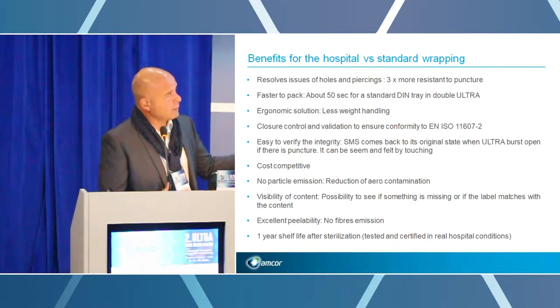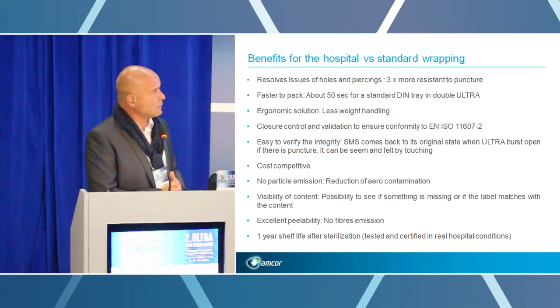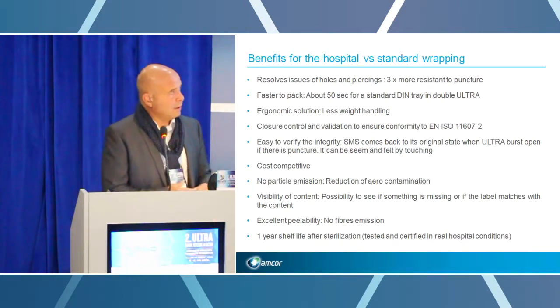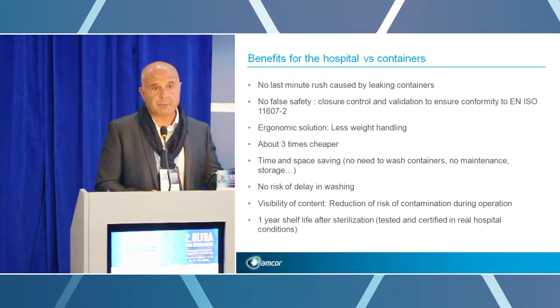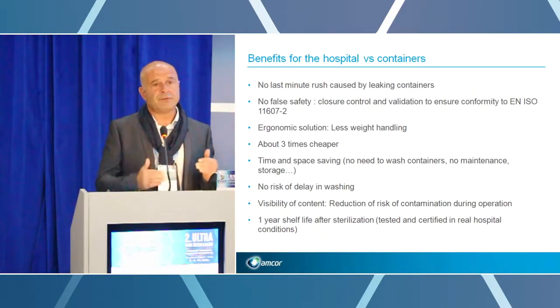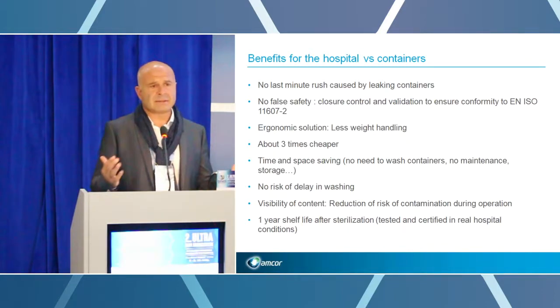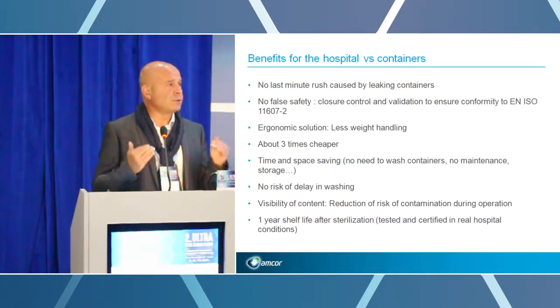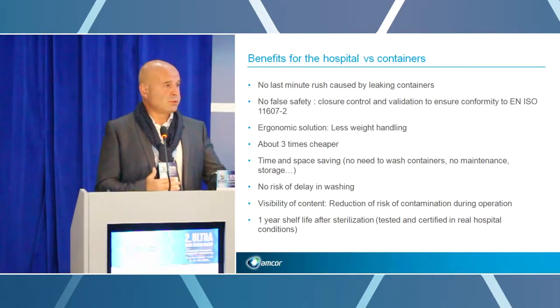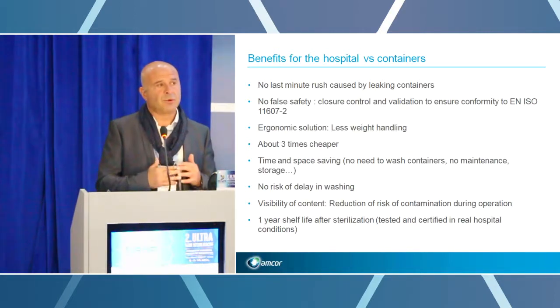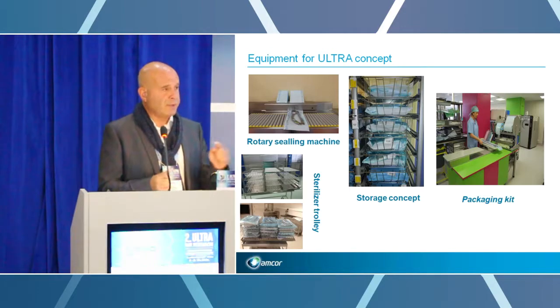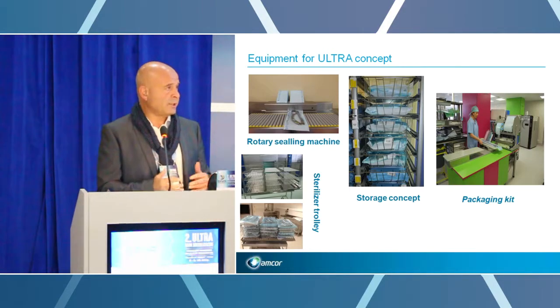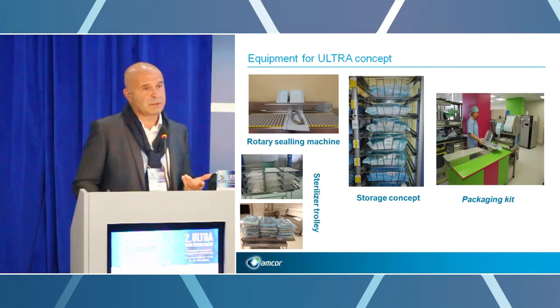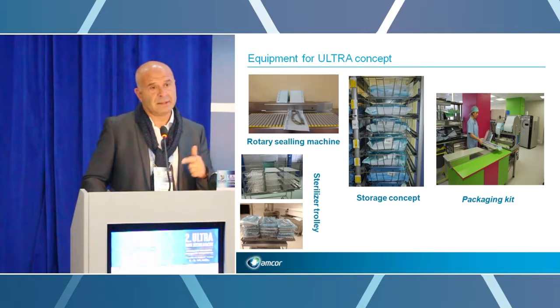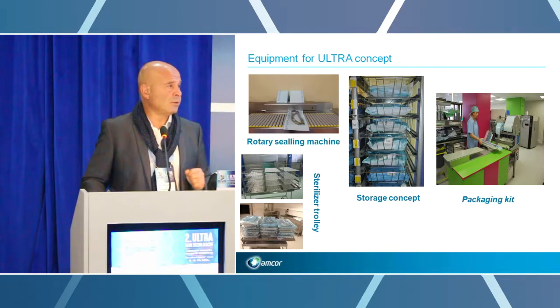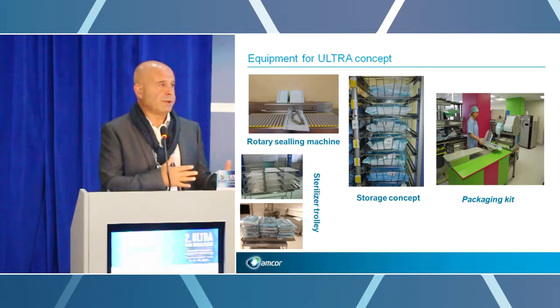This is some equipment to combine with the Ultra concept, like the sealing machine, like the packaging kit, and the storage, because storage is very important. If you use the packaging and you don't have good storage, it's possible you have the best resistance quality of material, but if you don't have good storage and good transportation to the operating theater, it's very difficult to conserve the sterility. It's the reason it's very important that you audit your storage in the operating theater and change it if the storage is not good. And in practice, it's very important to educate the nurses and the people in the operating theater about the storage. It's very important.